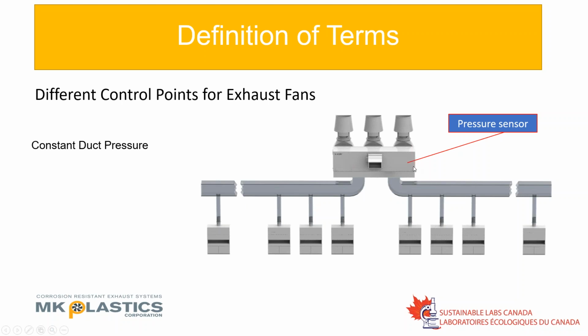So we are picking a pressure here, inches of water gauge, that is going to ensure that the fume hood at the furthest point is achieving its 100 feet per minute face velocity by controlling the lab control valve, or providing enough air through the lab control valve to do that without it going into alarm. This is normally a very broad brush approach, and so it is quite coarse in its control. So all we're doing is taking a pressure, saying it's 5 or 6 inches of static pressure, and we are guessing that everything's working because we're not getting any alarms on our fume hoods.